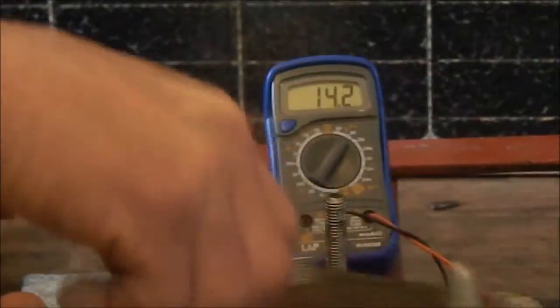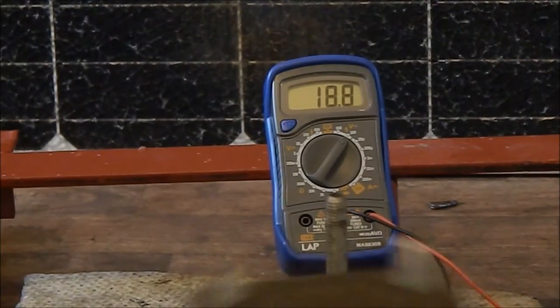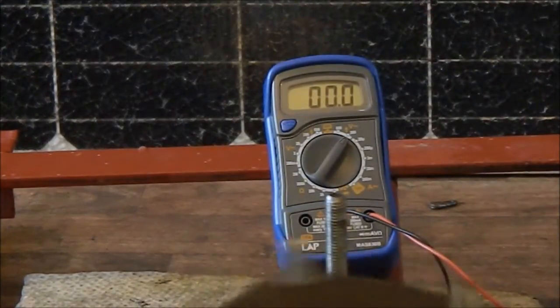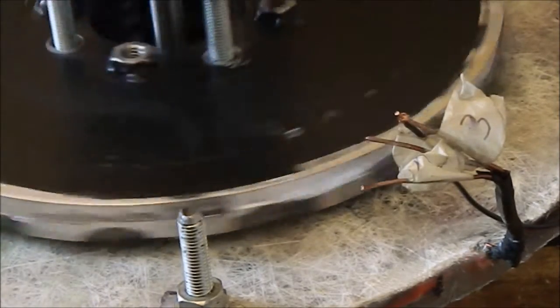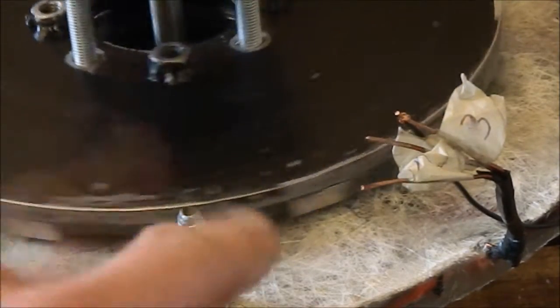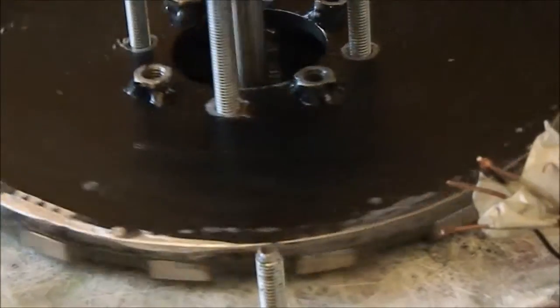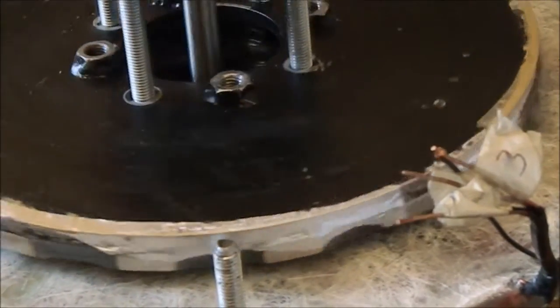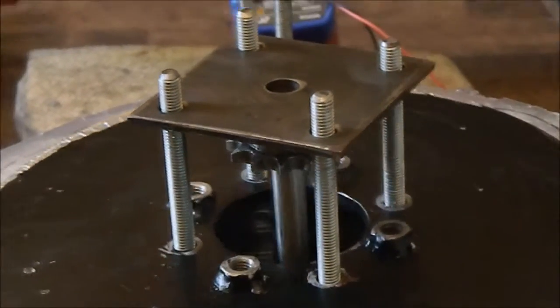There you go. See that? The lower reading, I believe, is because that's the third phase. The one I've marked three. Yeah, I've marked them one, two and three. And the one marked number three has basically the problem because the coils got dislodged. So that seems to offer up less on the AC side, about 22 rather than 26. But there's some loss to be expected.